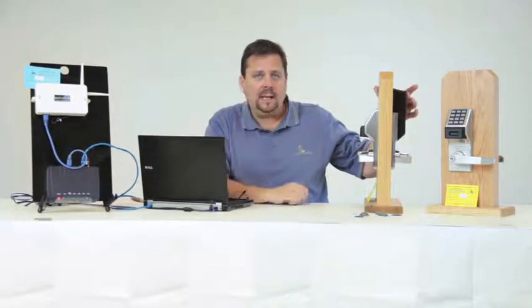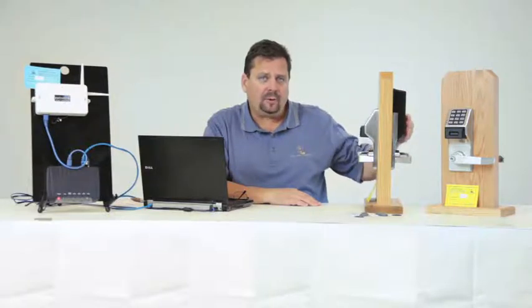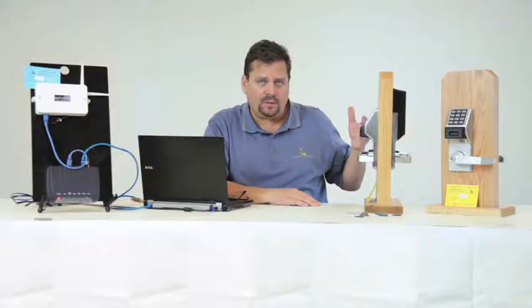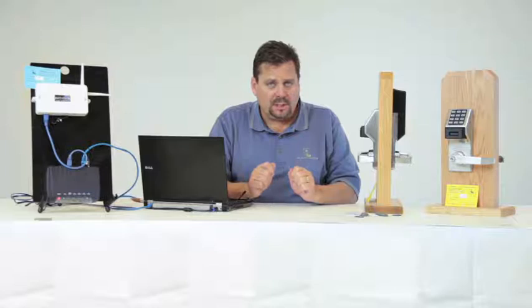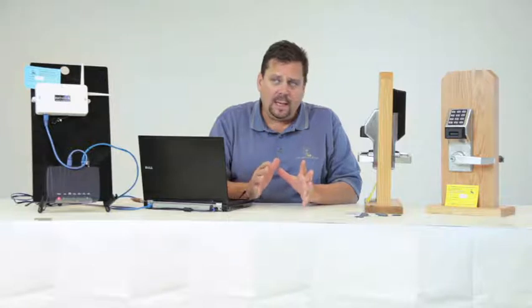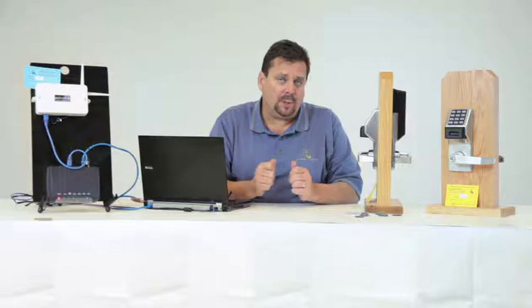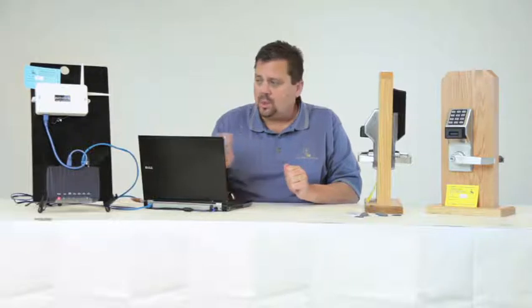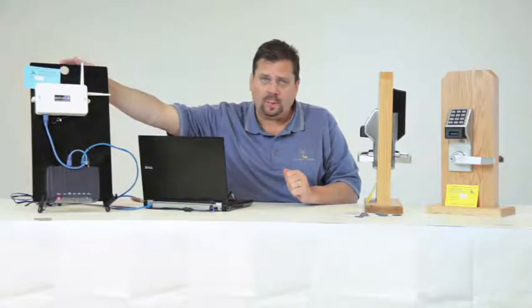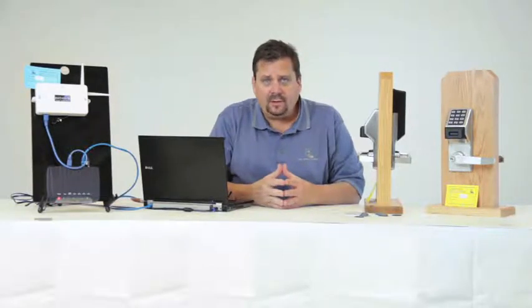Inside these locks there is a 900 megahertz radio powered by four C-cell batteries — this version is the prox version. When installing, it's important to select the correct locations. Choose a secured area for the gateway — an office or closet — near the ceiling, somewhere that no one will accidentally unplug the data or power connection. Each gateway comes with a blue card containing the MAC address — the identifying address of that particular gateway.